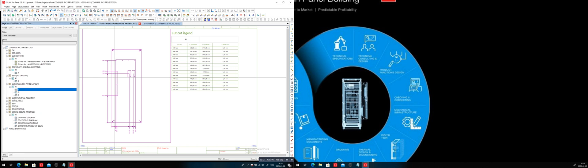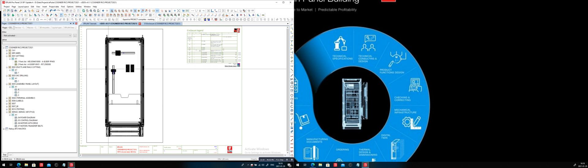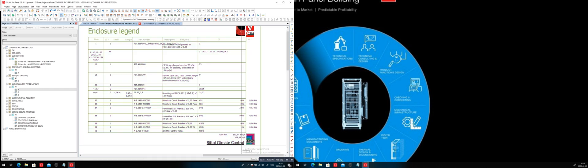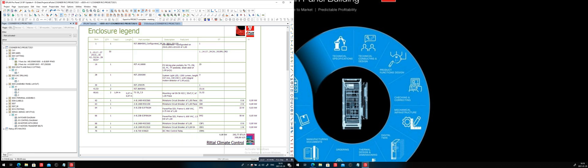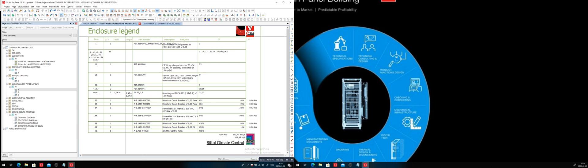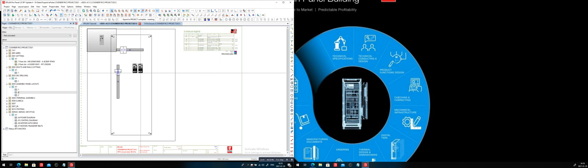Now obviously at one point in time you will have to assemble the backplate. So put some components on them and interestingly you will see that as I look at the global panel I can look at this detailed list and I can right away also see how much cooling do I need in this particular panel. I don't have too many components right now placed that actually do consume or have a power consumption but if I would they would all add up and the more I place on the panel the more come out here. This here is probably what's on the door. I haven't placed anything on the door.